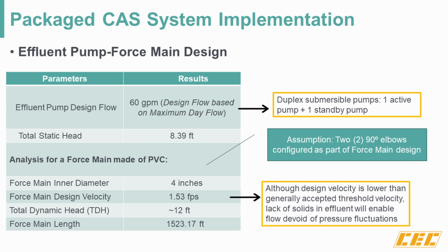So this segment looks at the effluent pump system that will convey the treated effluent into the creek. So again, the operational parameters are similar to what we looked at in the influent pump station. Once again, it will be a two-pump system. One pump will serve as backup. But in this case, it is just a submersible pump. There is no grinder component associated with the pump.